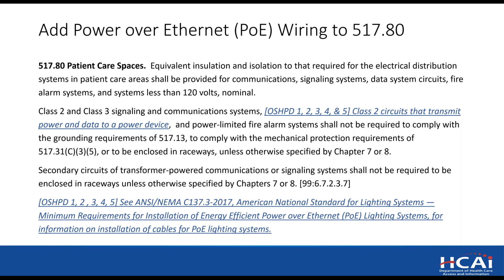Power over Ethernet. This is something that there had been lots of discussion by some individuals, and we appreciate everybody's input. We are now clarifying in the code that the class 2 circuits that transmit power and data for devices do not need to be mechanically protected. So we see that the model code is going in this direction. We see that nurse call and fire alarm are power over Ethernet systems that do not have the mechanical protection. So we've just brought the power over Ethernet lighting to match that. Next slide, please.